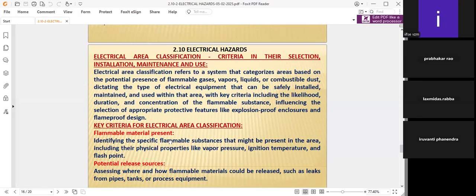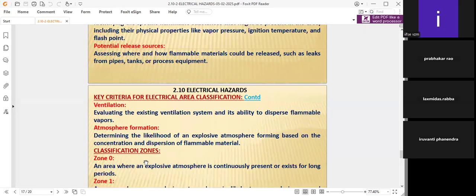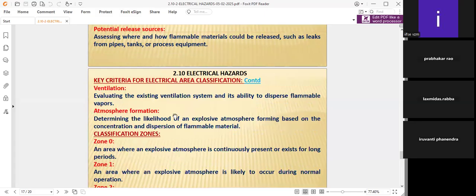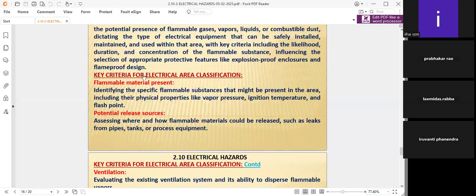Here the flammable material was already discussed, along with the potential release of sources. Here I want to discuss some areas like ventilation and atmosphere formation. For example, the three criteria of area classification are whether flammable material is present or there is a potential release of source. With these three things, we have to identify which class the area comes under. If flammable material is present, we have to see that the equipment is taken care of. If there is a potential release of source, we have to see that the equipment is arranged accordingly.